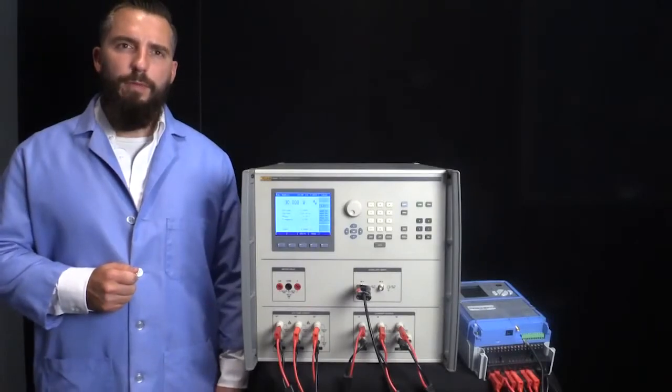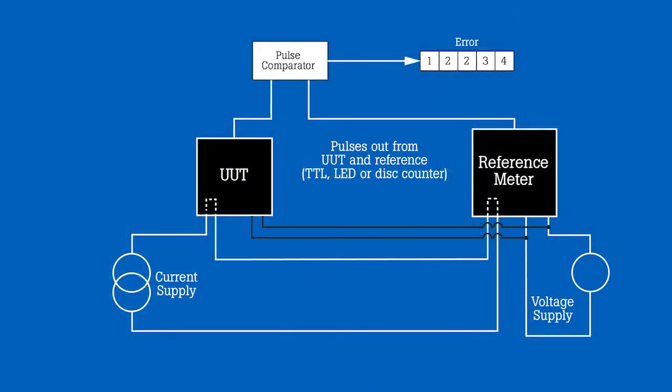Calibrations are traditionally performed using a reference measurement technique where a known amount of energy is simultaneously supplied to a reference meter and the meter under test. A reading from the reference meter is then compared to a reading from the UUT and the error is calculated.